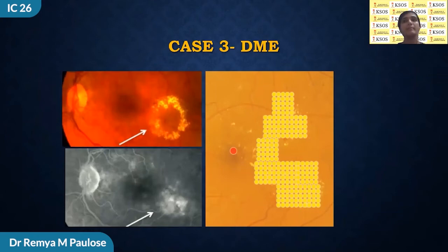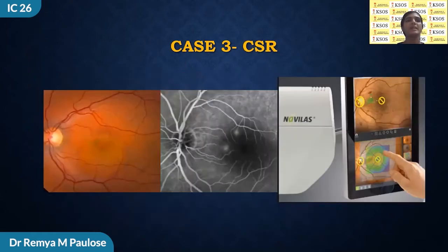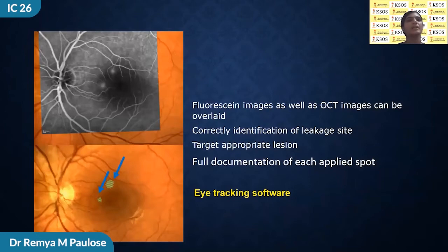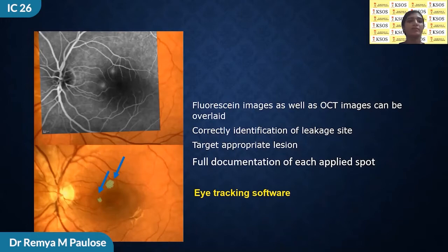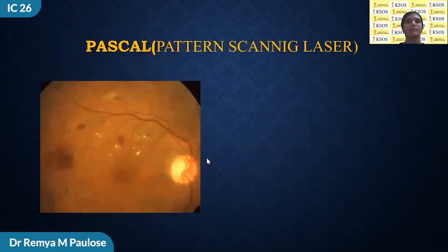Micropulse laser can also be used in cases of diabetic macular edema, wherein according to fluorescent angiography these points of diffuse leakage can be marked and micropulse laser can be delivered in a grid pattern. A navigated laser is a unique platform that combines color, infrared, and fluorescent fundus imaging to produce the most precise laser treatment. Fluorescein images as well as OCT images can be overlaid correctly to identify leakage points and target the appropriate region adequately while minimizing damage to healthy tissue. Eye tracking software is incorporated, which allows precision of laser treatment. NAVILAS also produces full documentation of each laser spot applied, ensuring true traceability and enabling pre-planned laser positions with automated execution of laser spots.